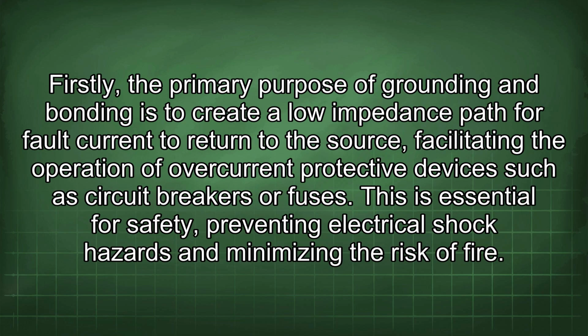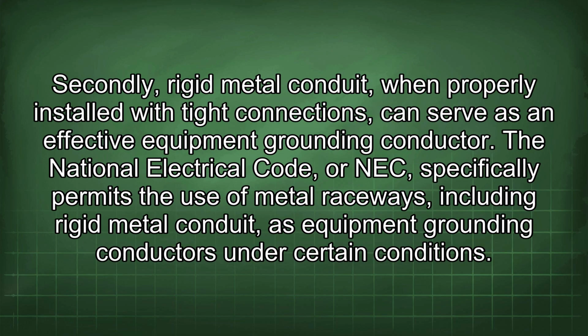Firstly, the primary purpose of grounding and bonding is to create a low impedance path for fault current to return to the source, facilitating the operation of overcurrent protective devices such as circuit breakers or fuses. This is essential for safety, preventing electrical shock hazards and minimizing the risk of fire. Secondly, rigid metal conduit, when properly installed with tight connections, can serve as an effective equipment grounding conductor.